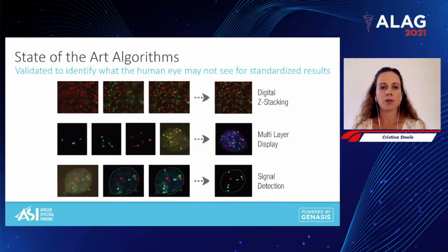As the scanner is capturing each individual filter, it's actually going through and Z-stacking. And these Z-stacking layers are customized by the lab and can be different between sample types. So you would want more Z-stacks on a paraffin tissue than is required for a cell suspension.